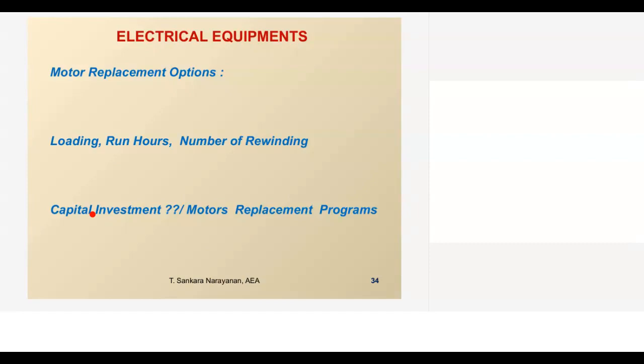Energy efficient motors are capable of taking care of VFD requirements, because normally when you are running a motor at a lower load, the ventilation is not fully adequate. That is why many of the motor manufacturers earlier restricted operating with a VFD at low loads. But today, wherever energy efficient motors are coming, these can take care of the VFD requirement. So that is the advantage.